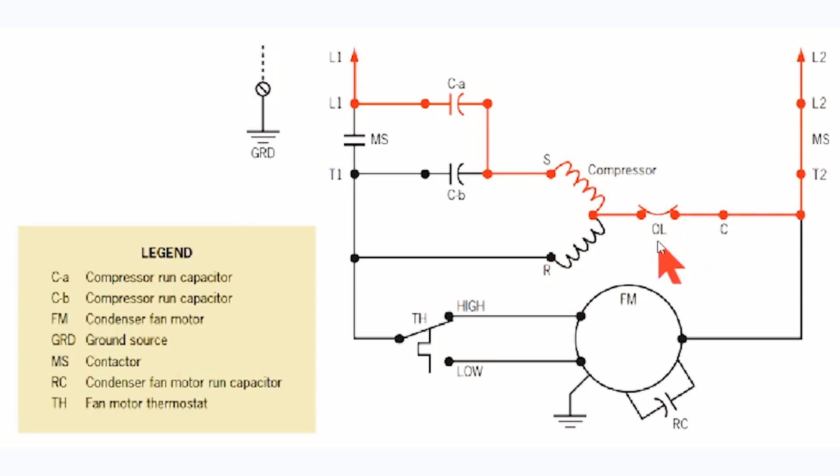What we have here is two run capacitors wired in parallel with each other. With run capacitors, if you wire two in parallel, the total microfarad capacity adds together. Say you need a 40 microfarad capacitor and you don't have one - you can use a 30 and a 10 in parallel and you'll get 40 microfarads. A lot of you use that every day.